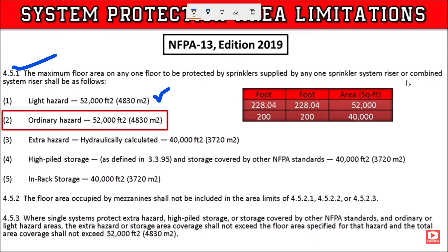For ordinary hazard and extra hazard area limitations, there are additional considerations. High pile storage as defined has its own area limits. The area occupied by mezzanines shall not be included in the floor area limits stated. Where a single system protects extra hazard, high pile storage, or areas covered by other NFPA standards, the combined ordinary and extra hazard areas shall not exceed the specified maximum square footage.